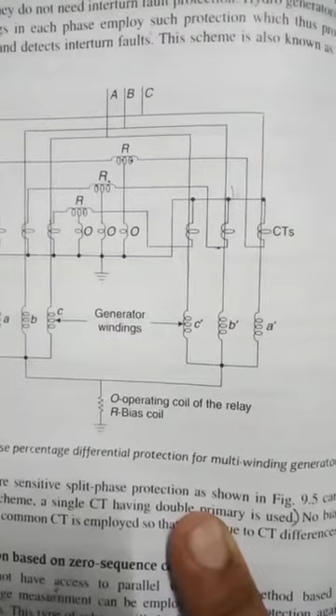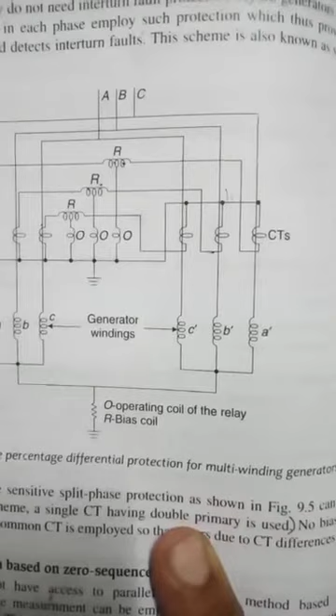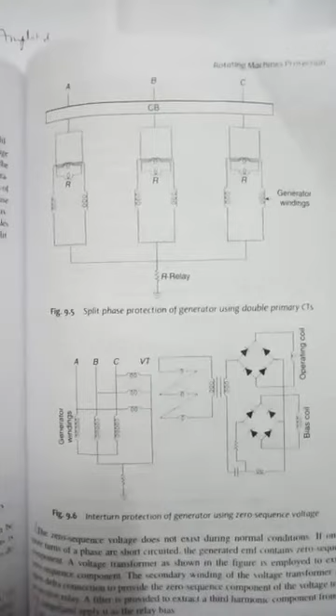The coils of modern large steam turbine driven generators usually have only one turn per phase per slot and hence they do not need interturn fault protection. Hydro generators having parallel windings in each phase employ such protection, which thus provides backup protection and detects interturn faults. So this scheme is also known as split phase protection. Here two diagrams are showing split phase protection of a generator using double primary CTs, and interturn protection of a generator using zero sequence voltage.